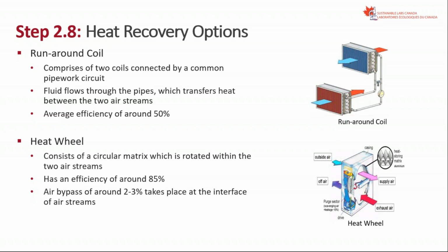One option is the runaround coil. Back east in the United States, this can give great success with a 1 to 2 year payback, and average efficiency is about 50%. You basically have two coils—one installed in the exhaust airstream, and a second installed in the outside air entering the building—and heat transfers through fluid between the coils. In some areas you can get a payback in 1 to 2 years; in coastal areas of California, this would give a payback of about 10 to 12 years. So depending on the area, it can be successfully used.